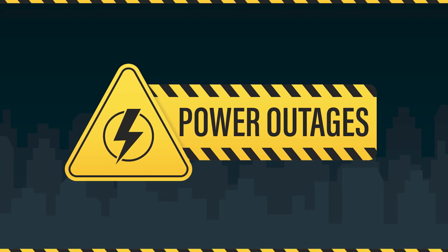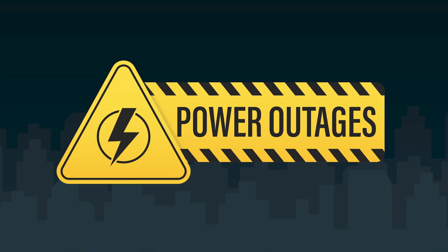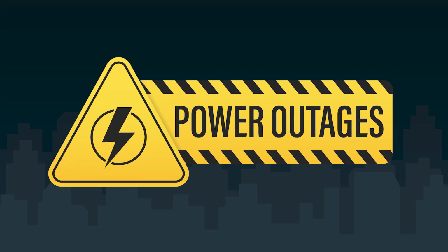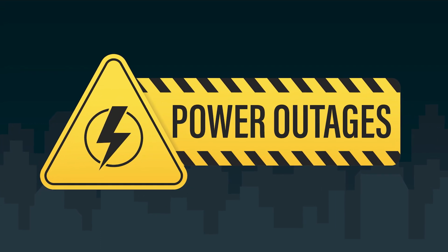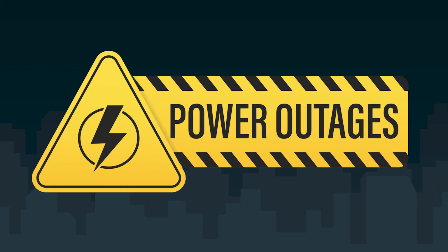A lot of times people don't even think about that. They're just used to power going out and having the stuff fail and have to replace equipment or having to replace the process material. And it's just the cost of doing business. But if you can avoid that, why not? Why not allow things to run smoothly, not take that hit? Even if it's relatively small, over time they add up and can justify a UPS.